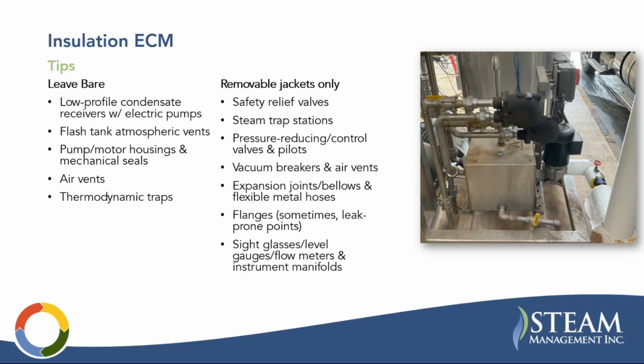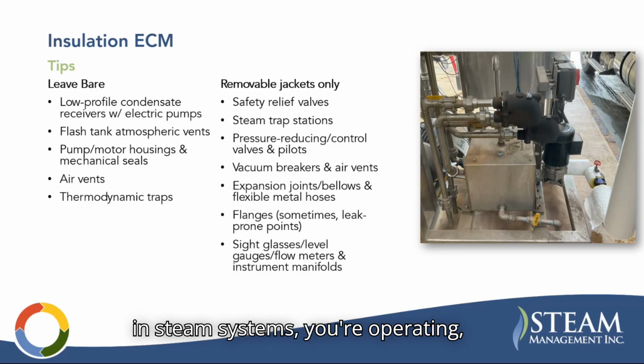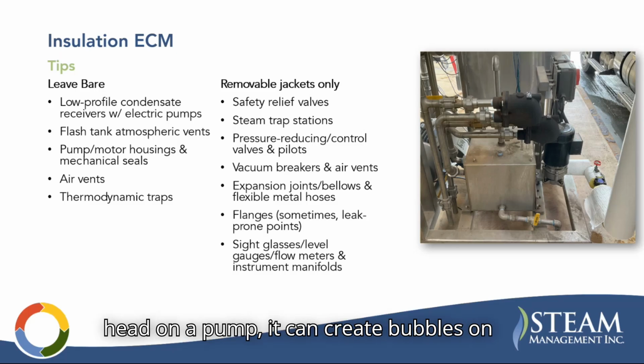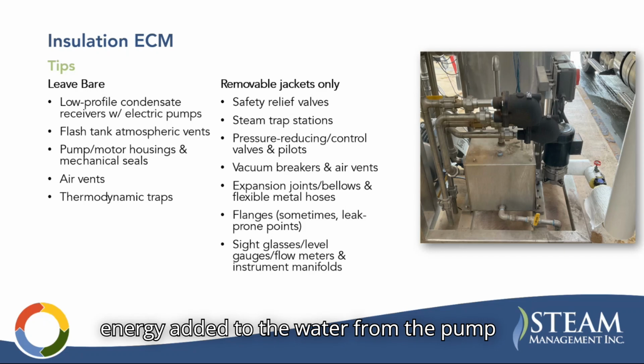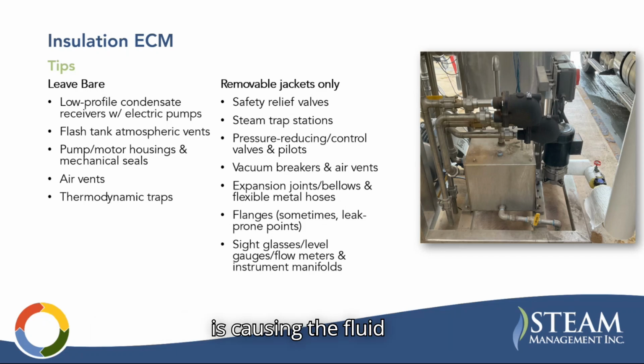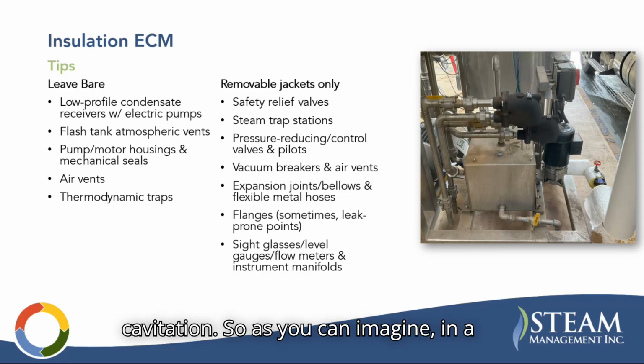And so in steam systems, you're operating... well, I'll back up. The concern is that if you don't have a lot of suction head on a pump, it can create bubbles on the intake, because the energy added to the water from the pump causes the fluid to turn to steam, and that causes bubbles, that causes cavitation. So as you can imagine, in a steam system, the condensate is very close to the saturation temperature of water, and so even a little bit of energy added can cause that cavitation.